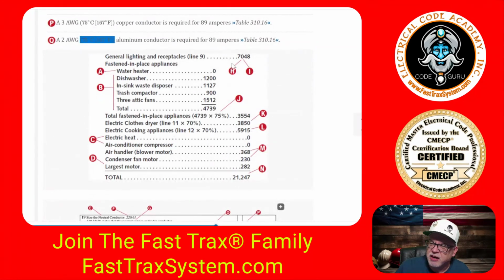And it must include the neutral calculation. So if you look right here, see how it says 7,048? Okay, so where did we get this? Well, in the standard method, we did 3 VA per square foot, right? And then we took the 2 small appliance branch circuits at 1,500 VA each, right? 210.11, okay, got to know those rules. And then we took the laundry circuits at 1,500 VA each, added it all up, but we were able to apply a demand factor to that. And in that demand factor, it was the first 3,000 at 100%, the next 117,000 at 35%, and the remainder at 25%.